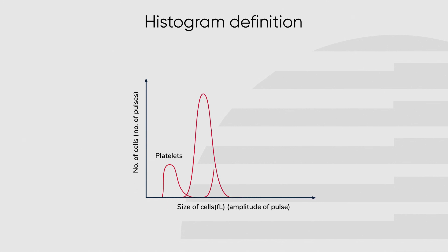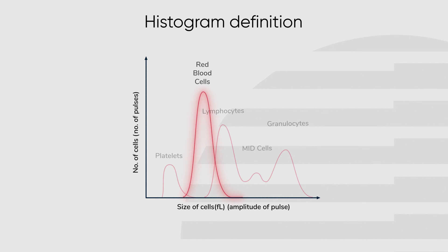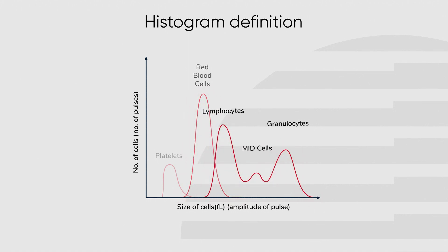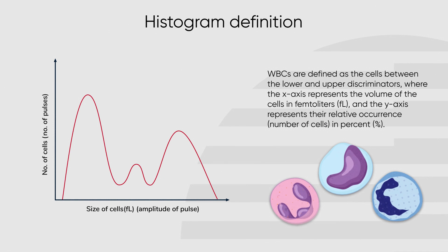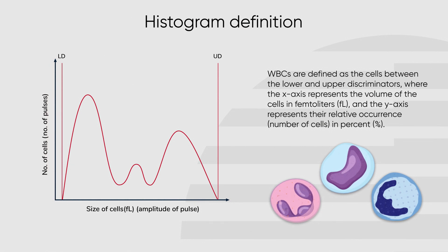In a three-part hematology system, blood cells are counted and assessed using impedance technology and displayed in three separate histograms: platelets, red blood cells, and white blood cells. White blood cells are defined as the cells between the set lower and upper discriminators, where the x-axis represents the size of the cells in femtoliters and the y-axis represents the number of cells.